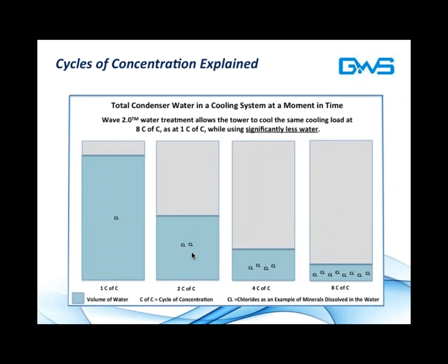We all know that in water, unless it's distilled, of course, there are dissolved minerals. And as you concentrate those minerals from 1 cycle to 2 cycles, you can see that the quantity of those minerals doubles. And that proceeds forward until you get to any number of cycles, upwards of 8, 10 or so, which is a theoretical maximum for efficiency in a cooling tower. You can see that this is the volume of water used to support the same cooling load. So you have approximately 75% savings when you run a cooling tower at 8 cycles versus 1.